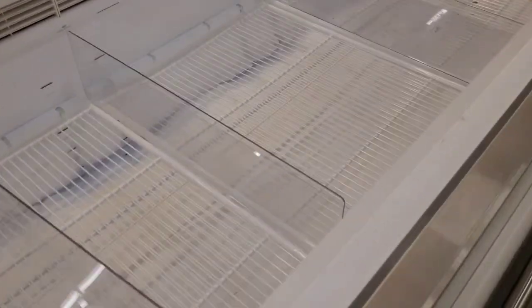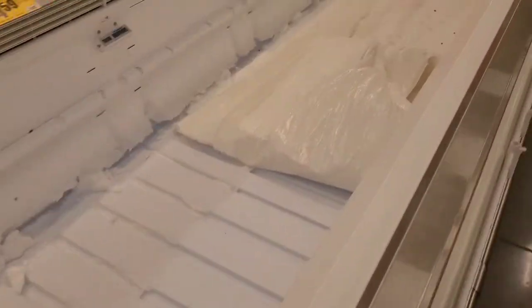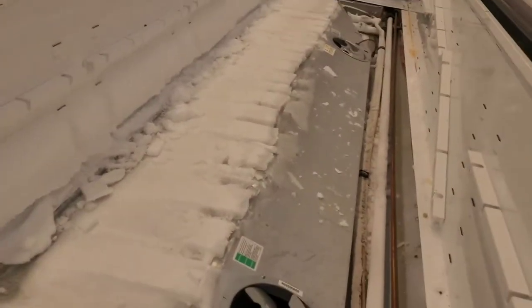Tonight at midnight, I've got a case that usually holds sausage that is empty because it's all froze up, reading at 42.8. Once I get all the covers off, I can see that it's got a whole bunch of ice everywhere. I start peeling back all this cloth stuff they use to cover it, lift off the covers, and it's nothing but ice. This evaporator is frozen bad — that's an incredible amount of ice.